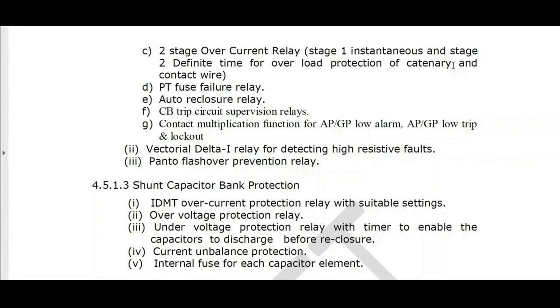Then what is IDMT? In IDMT, whenever the current crosses 2 amps, a timer will start. But what should be the time? Is it 5 seconds? It is not 5 seconds. It's actually dependent on the magnitude. For example, if the current is 10 amps, trip in 1 second. Or if the current is 5 amps, trip in 3 seconds. So you can find that the time keeps changing depending on the current. The greater the current, the lesser the trip time. The lesser the current, the greater the trip time. So this is the difference between IDMT and definite time.